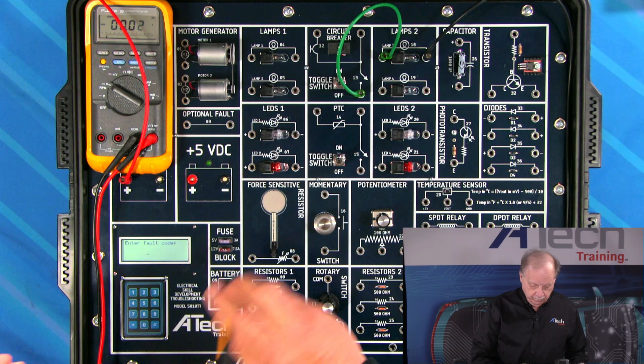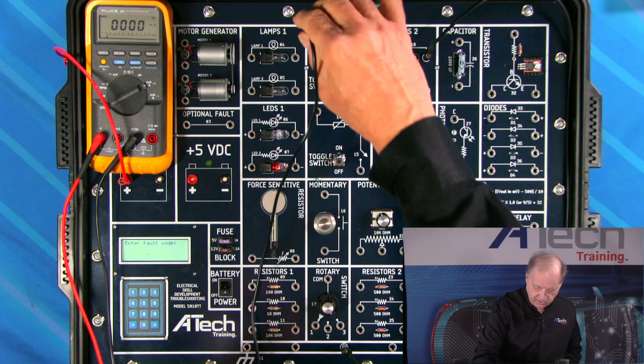So I'm going to check the feed side of the current. I have to move my lead all the way over to current. I'll take my black lead and put it at the circuit breaker, check the circuit up here, and turn it back on. I have a 260 milliamp draw.